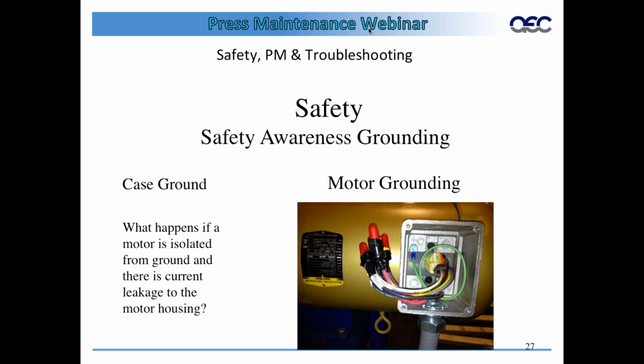So a good case in point is a motor that has a metal casing on it. You'll see in this photo that there are the current carrying conductors. This is a 3-phase motor that runs into the windings. Now the motor internally is isolated from the case, isolated from ground. But if something wore, something broke down, something shorted, and it caused the windings or any other part of the electrical system within the motor to touch the case, then that case is also at the potential voltage of what's coming to it.